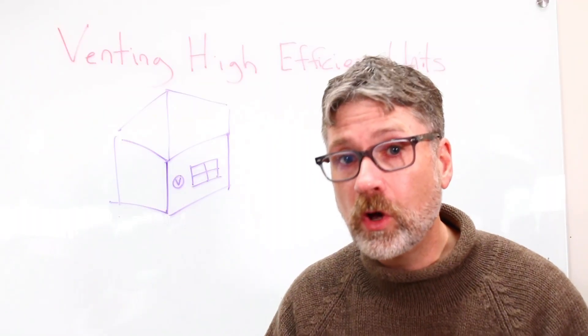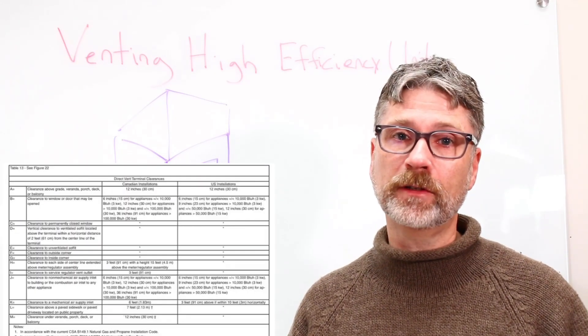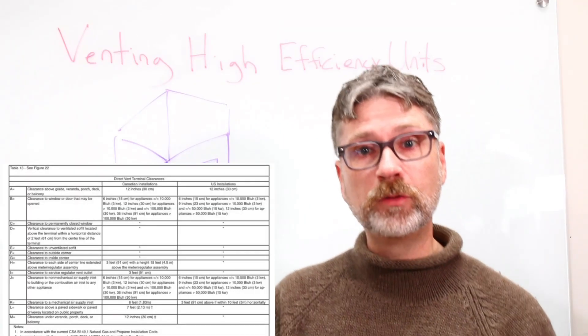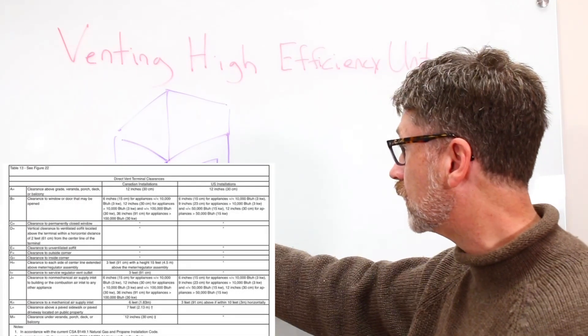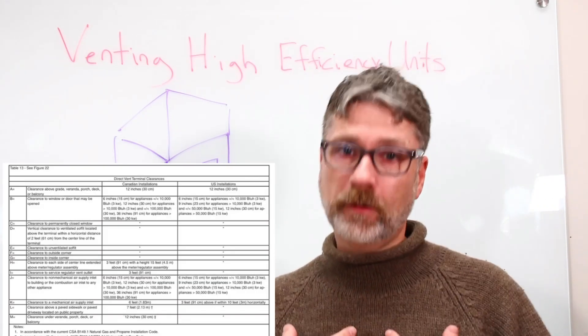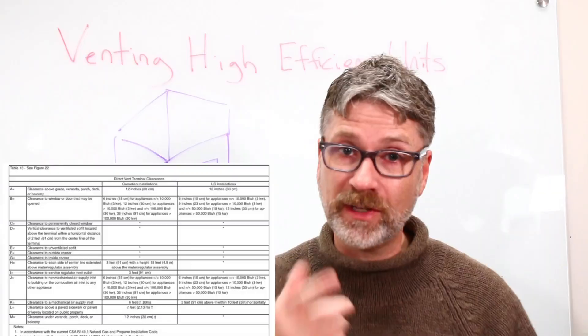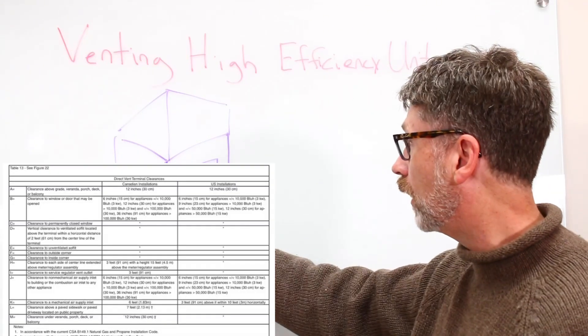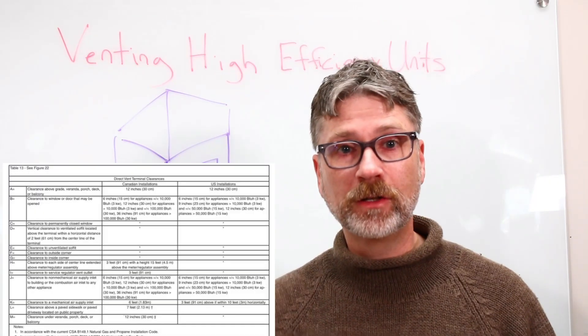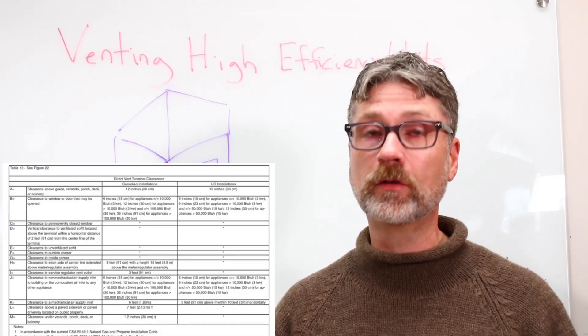Your state and local codes may also be different. So for example, the U.S. code says 12 inches to a window that operates. That's the distance between the vent and the window. Whereas your local code, what we have here in Tennessee for example, says three feet, considerably larger distance between the window and your vent. Find the chart, use the chart, and be aware of your local codes.